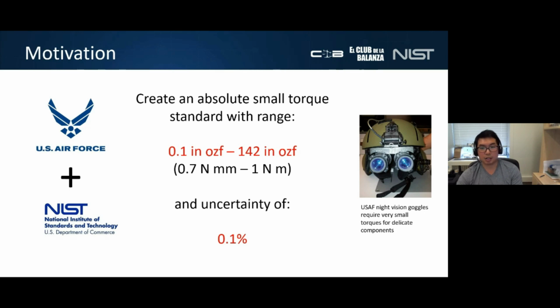Around the same time the U.S. Army collaboration on the Kibble balance began, the U.S. Air Force began funding us for 3 years to develop an absolute torque realizer, also based on the Kibble principle, for directly realizing 0.1 to 142 inch-ounce force with an uncertainty of 0.1%, for directly calibrating sensitive torque watches, screwdrivers, and wrenches.